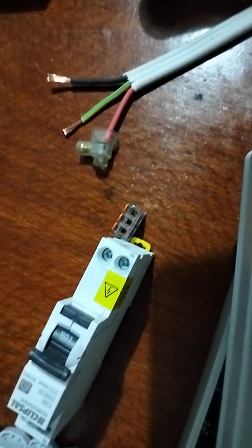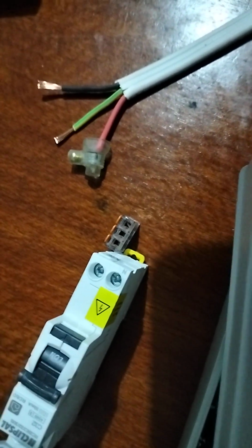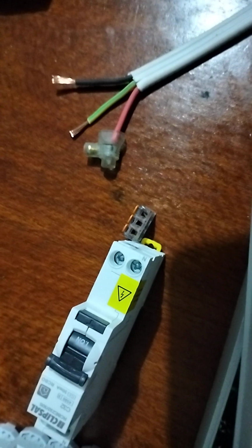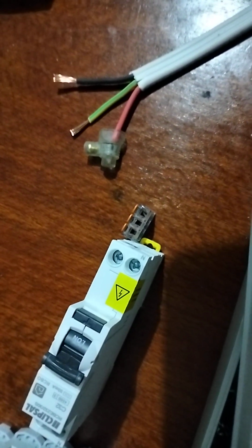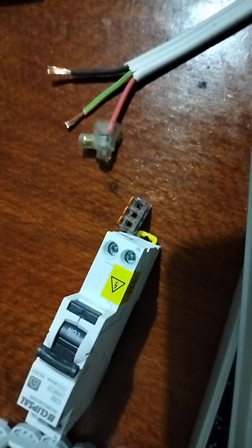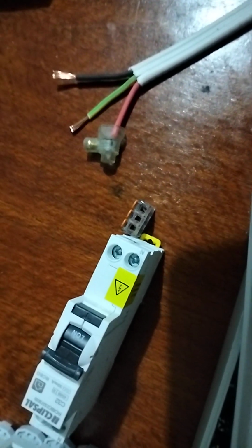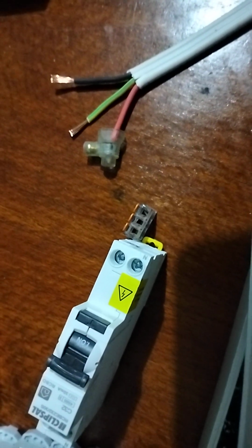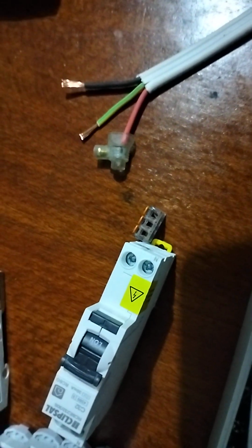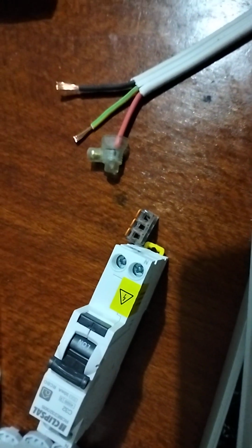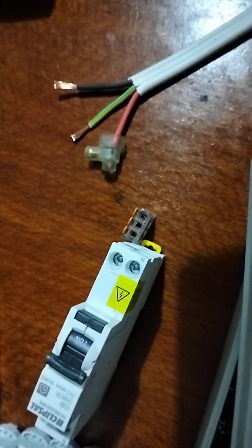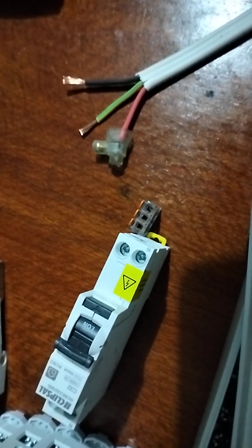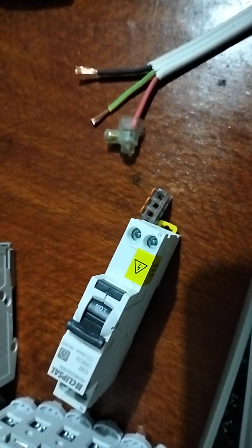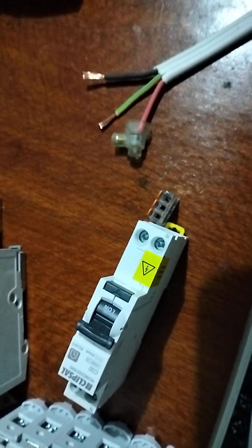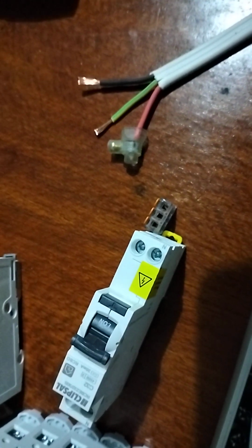I'd recommend, if you're working with lethal power, get an electrician to at the minimum check your work, because even after we've done our wiring, we carry out comprehensive tests with insulation testers, earth leakage testers, and fault loop impedance testing. There's at least 4 different tests we will do on an installation, and we check every wire and make sure it all works. So I don't care how good you think you are, you still got to test and verify all your circuitry.